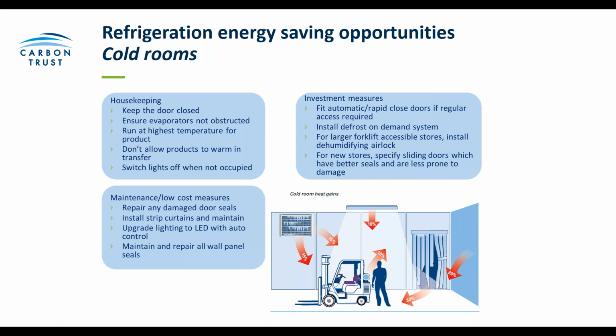In terms of investment measures, again, automatic rapid closing doors are the thing to invest in, as well as a defrost on-demand system, which we have a case study for a little bit later on in the content. For larger spaces, forklift accessible cold stores are an example. Incorporate an airlock or anti-chamber with dehumidification into the forklift entrances, and this basically reduces ice buildup and the need for any defrosting that you could potentially avoid. When purchasing new equipment, keep in mind that sliding doors are probably the best doors to use with a better seal, and they're also less likely to get damaged.